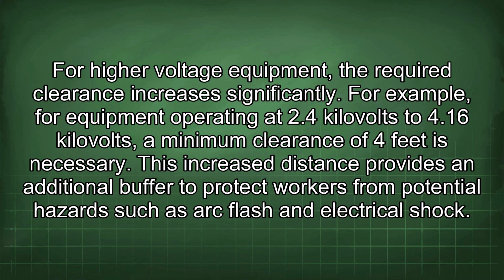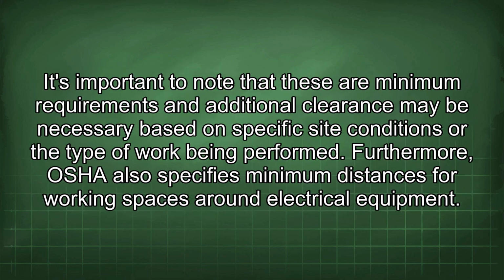For higher voltage equipment, the required clearance increases significantly. For example, for equipment operating at 2.4 kV to 4.16 kV, a minimum clearance of 4 feet is necessary. This increased distance provides an additional buffer to protect workers from potential hazards such as arc flash and electrical shock. It's important to note that these are minimum requirements and additional clearance may be necessary based on specific site conditions or the type of work being performed.